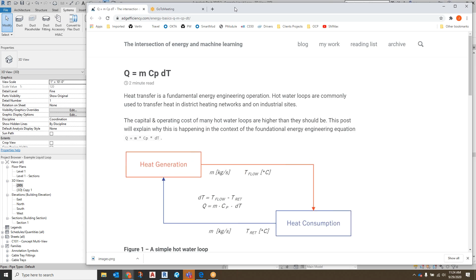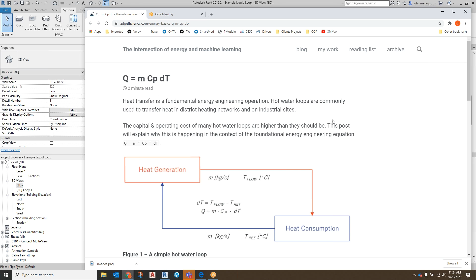When we're selling liquid solutions to our customers, we're looking at how to retrofit our existing design, how we can pull out a CRAH and use the tap-offs to feed a CDU, or in some instances go with elevated temperatures directly to the rack, bypassing the CDU off that tap-off. We also provision future positions on our branch loops and headers, so we can provide future positions to CDUs. Understanding the trade-offs of going with larger capacity tap-offs helps us understand what capacity we could cool with liquid solutions.